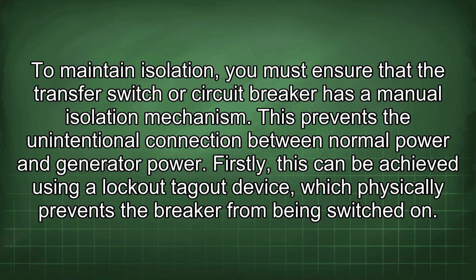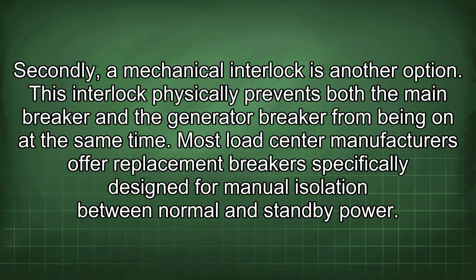To maintain isolation, you must ensure that the transfer switch or circuit breaker has a manual isolation mechanism. This prevents the unintentional connection between normal power and generator power. Firstly, this can be achieved using a lockout-tagout device, which physically prevents the breaker from being switched on. Secondly, a mechanical interlock is another option. This interlock physically prevents both the main breaker and the generator breaker from being on at the same time.